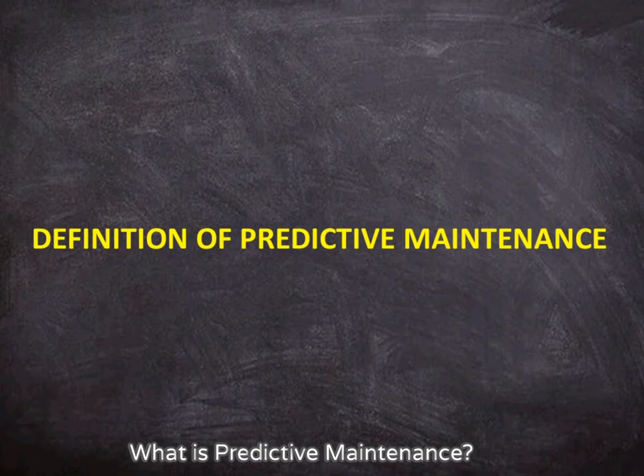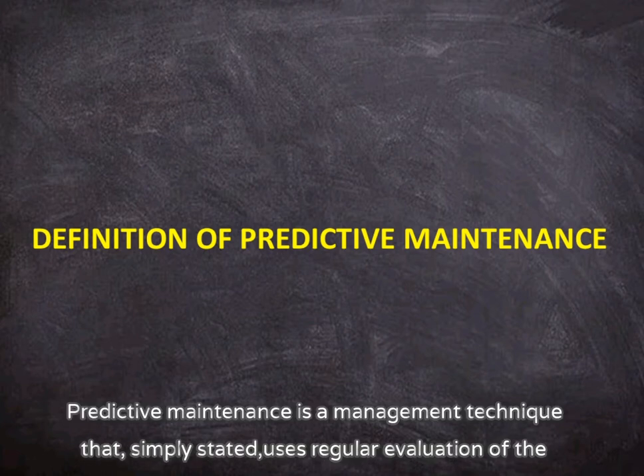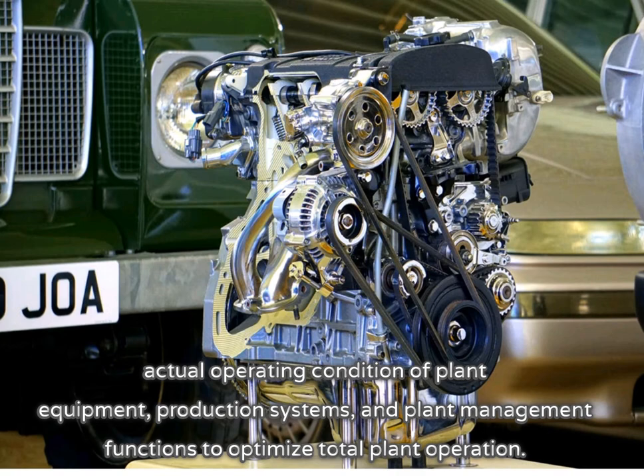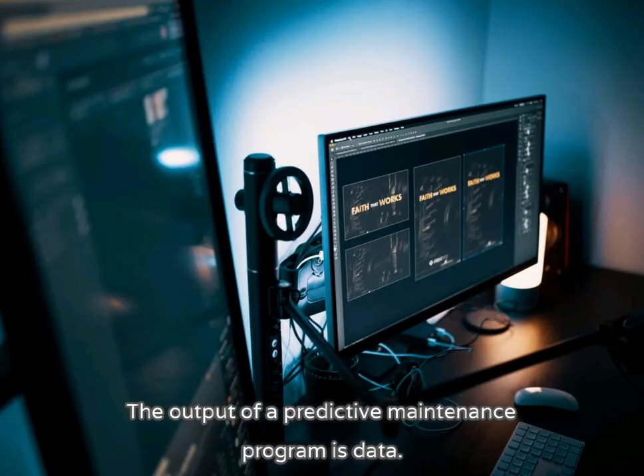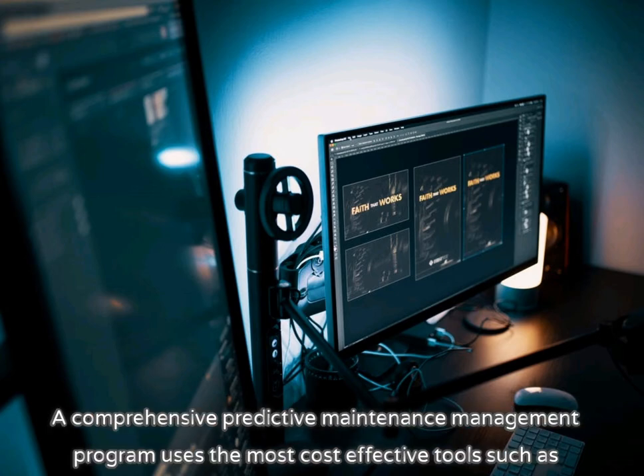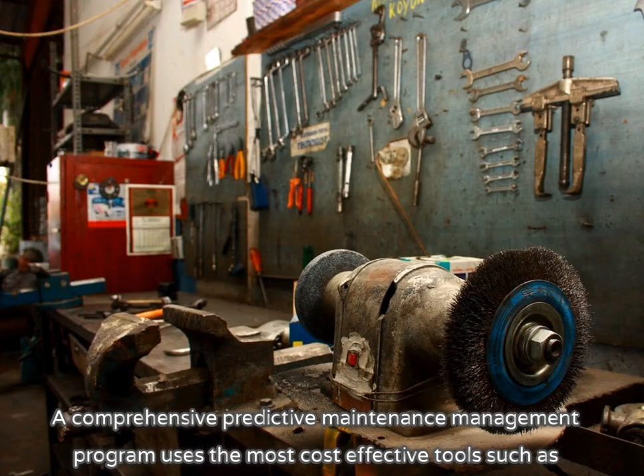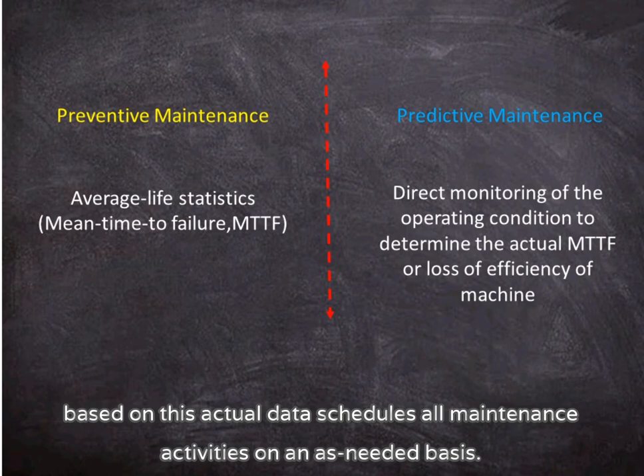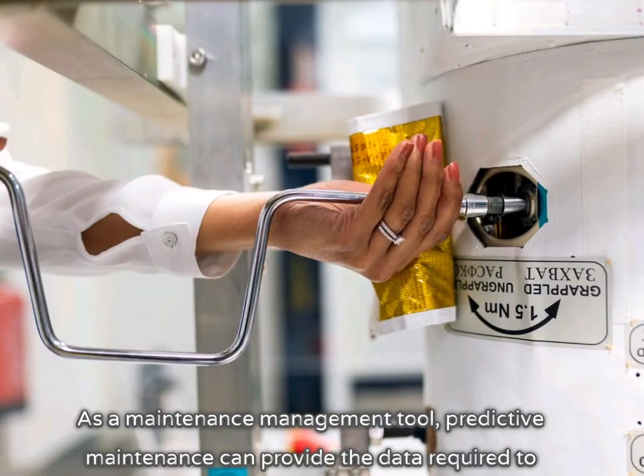What is predictive maintenance? Predictive maintenance is a management technique that, simply stated, uses regular evaluation of the actual operating condition of plant equipment, production systems, and plant management functions to optimize total plant operation. The output of a predictive maintenance program is data. A comprehensive predictive maintenance management program uses the most cost-effective tools such as vibration monitoring, thermography, and tribology to obtain the actual operating condition of critical plant systems and based on this actual data schedules all maintenance activities on an as-needed basis.